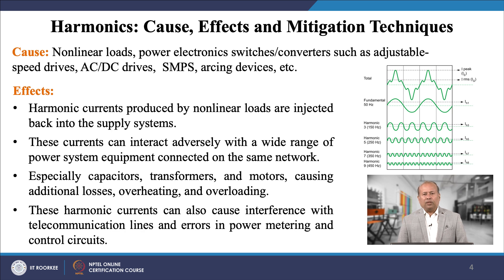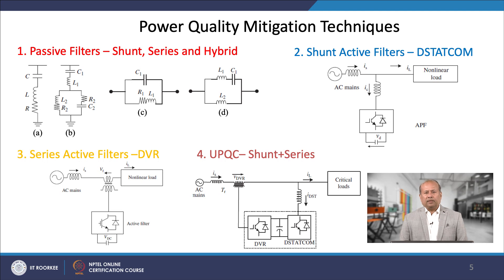As per the IEEE standard 519-1992, harmonics should be less than 5 percent. Therefore, in order to compensate harmonics, a number of mitigation techniques are available in the literature. They are passive filters, series active filters, shunt active filters, and unified power quality conditioner. These filters compensate both voltage and current related power quality problems as per the requirement. However, each has its pros and cons.